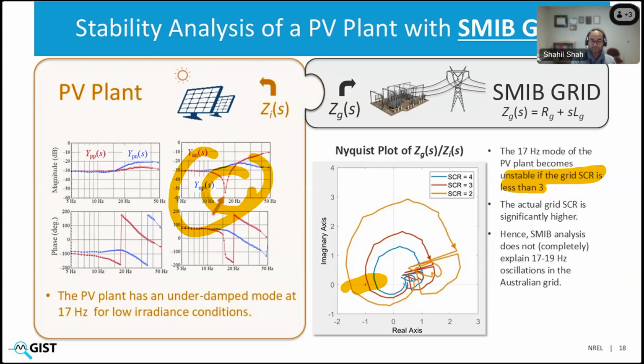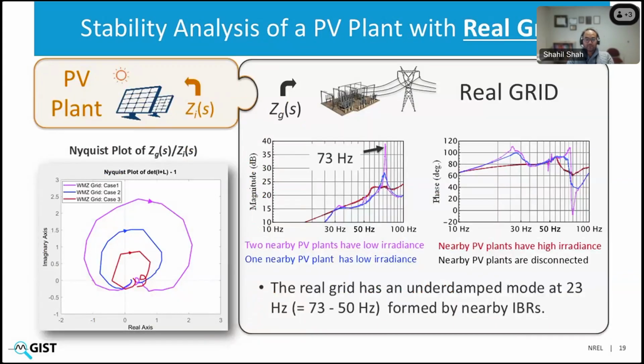Now that is good. We got some insight that some of these plants are probably the source of oscillations. But the actual grid SCR based on positive sequence analysis was significantly higher. So that still doesn't completely explain the source of oscillations. So we go to step 3, where we take this IBR impedance response, or basically the puzzle piece, which represents the worst impedance response of the IBR in terms of stability, and try to match it with different grid impedance responses, which is on the right.